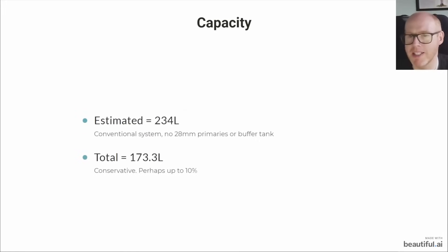Now, before we get into the recommended for a Vaillant heat pump, we estimated 234 litres and my total came at 173.3. So if we're using these rules of thumb to measure, we're probably going to the wrong side. We want more system volume for our heat pump to run really optimally and efficiently. This estimate is for a conventional system not with a buffer tank and not with 28 mil primaries, so it's way off once you start adding those in.